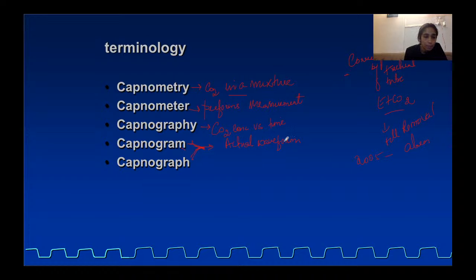Now, for this capnometer, there are certain standards that have to be followed. The carbon dioxide reading has to be within plus or minus 12% of the actual value, or plus or minus 4 millimeters of mercury. So this can be the variation.